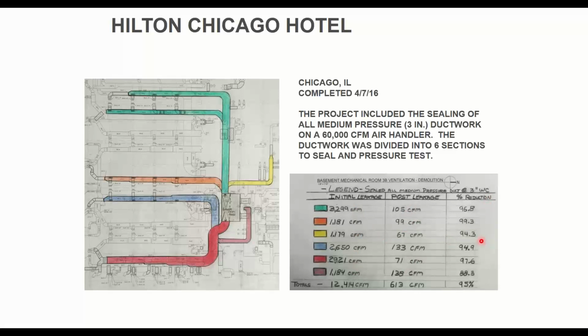And you're getting between 94 and 99% reduction of leakage. And in total, it went from 12,000 CFM leakage down to 600 CFM, which was a 95% improvement. They literally have 12,000 CFM that used to be leaking under the floor, being wasted, that is now going into the spaces. So significant improvement in airflow in the spaces and obviously reduced energy costs to go with that. This air handling system was like an 80-year-old constant volume system that they converted over to VAV. But the ductwork, it is what it is. You couldn't really get back to it again. So this solution really worked really well.